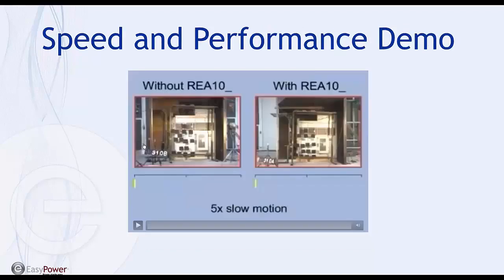So let's take a look at just how fast the REA arc flash is compared to a traditional instantaneous relay operating for a half second, which is the IEEE standard for testing. So we'll run the video and we'll show you that the standard is to contain the explosion and to prevent a fire for a half a second 3-phase voltage arc flash. So you can see the significant difference that the operating time of the REA makes compared to a traditional relay. So this is 5 times slow motion.